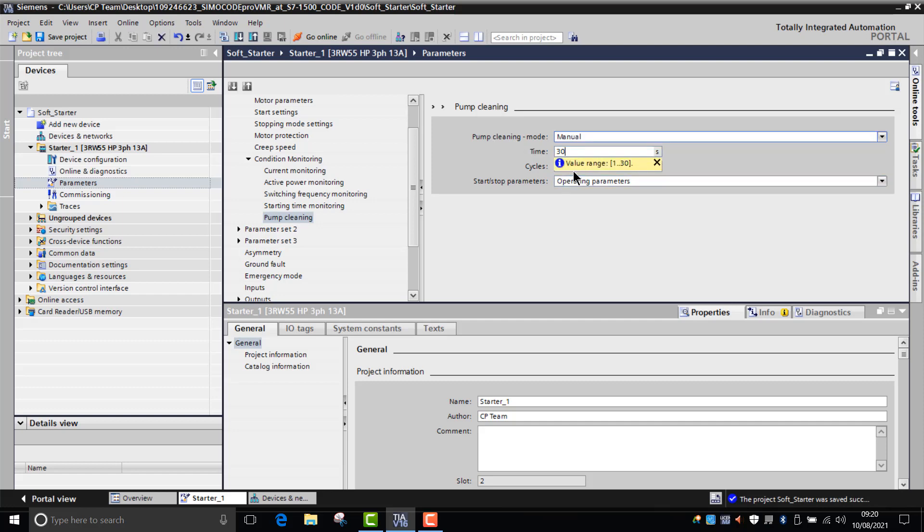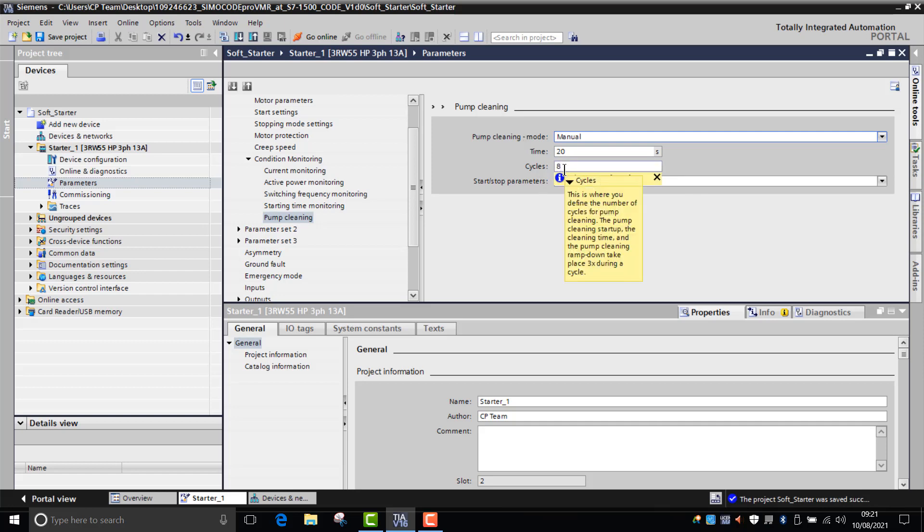You can select a time setting range here from 1 to 30 seconds, so we might want it to cycle for 20 seconds. Then from here you can decide how many times that device enters a forward and reverse sequence. It can range from 1 to 10, so we'll have that parameter as 8.